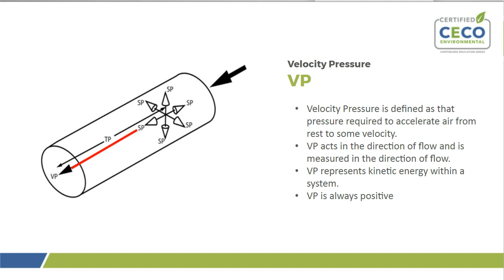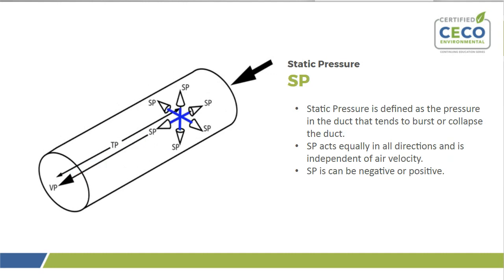Velocity pressure is defined as that pressure required to accelerate air from rest to some velocity. Velocity pressure acts in the direction of flow and is measured in the direction of flow. Velocity pressure represents kinetic energy within a system. And finally, velocity pressure is always positive. Static pressure is defined as the pressure in the duct that tends to burst or collapse the duct. Static pressure acts equally in all directions and is independent of air velocity. And static pressure can be negative or positive.